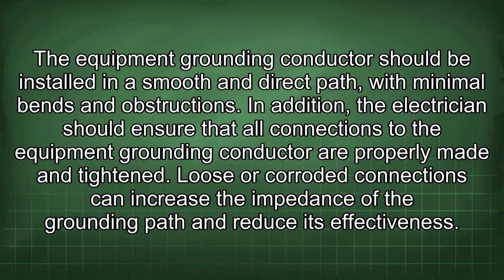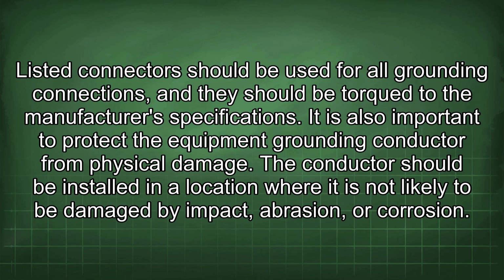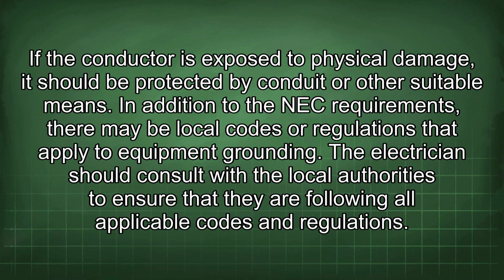Loose or corroded connections can increase the impedance of the grounding path and reduce its effectiveness. Listed connectors should be used for all grounding connections, and they should be torqued to the manufacturer's specifications. It is also important to protect the equipment grounding conductor from physical damage. The conductor should be installed in a location where it is not likely to be damaged by impact, abrasion, or corrosion. If the conductor is exposed to physical damage, it should be protected by conduit or other suitable means.